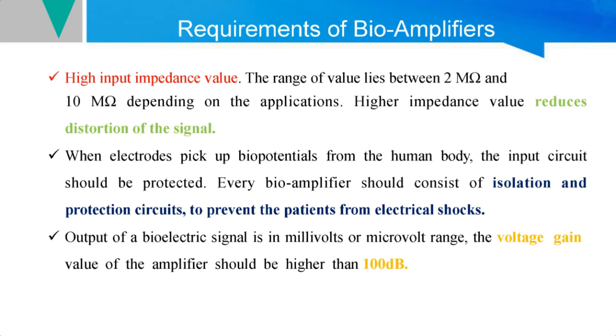Another very important requirement is that the bioamplifier should have an isolation and protection circuit, because the input is the patient. The amplifier must be designed so that it does not give any electrical shocks to the patient. If there is any improper functioning of the amplifier, it could revert back and affect the patient's body. Additionally, the output voltage gain should be very high — greater than 100 decibels.